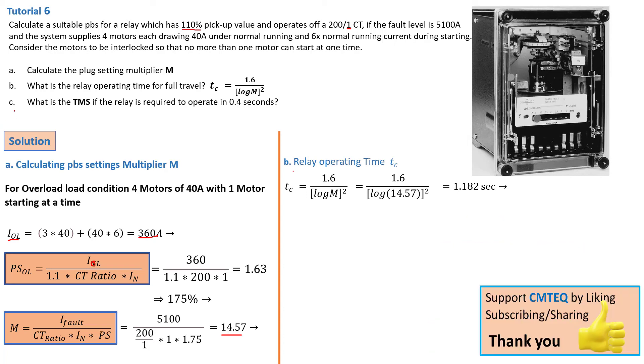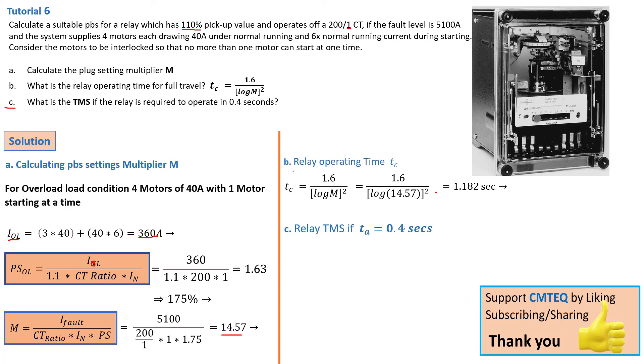Okay, now we move on into the last and third question, number C. That is what is the TMS if the relay is required to operate in 0.4 seconds. So the 0.4 second is actually the actual time. So we know that TMS is equal to TA over TC. And replacing all the values, that means that TMS is equal to 0.34 seconds.